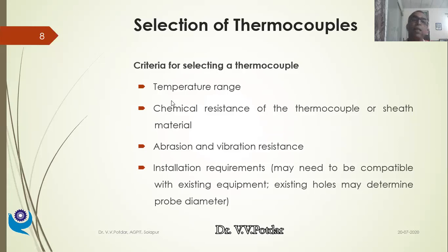What is the temperature range that I'm interested in? What is the corrosion resistance or chemical resistance of the thermocouple or the sheath material, the enclosing material? Abrasion, wear, how much can it be, where I am going to use it, and vibration resistance. Installation requirements may need to be compatible with existing equipment. Existing holes may determine probe diameters.